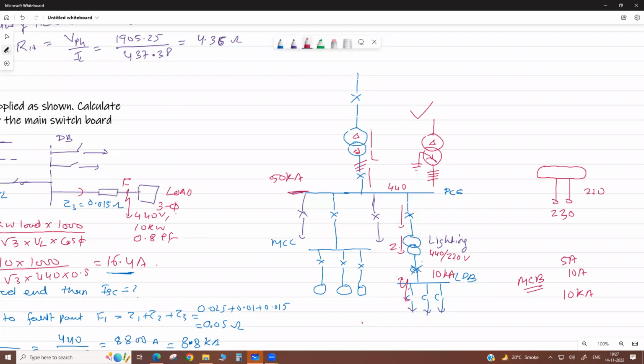Otherwise, this switch would not be of such a small size; it also becomes bigger if the fault level is high in the lighting circuit. Okay. That's why, to reduce the fault level in the lighting circuit, we insert a series impedance here, then the short circuit current at the lighting level is reduced. Okay, so this is the purpose of the lighting transformer.